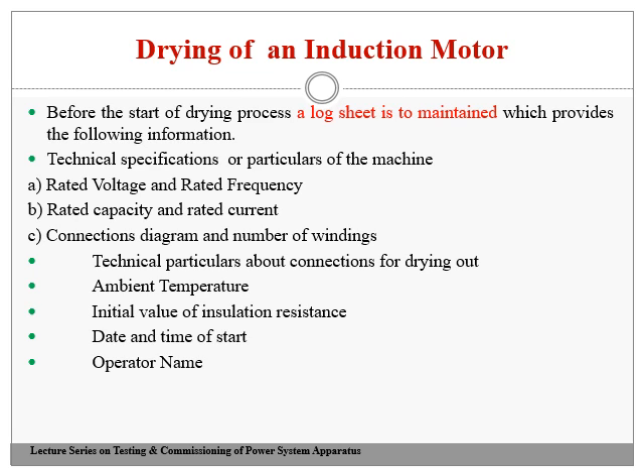Therefore, the technical details of the motor or equipment which comes up for the drying process are noted down in a log sheet. The technical particulars about the connections for drying out, ambient temperature, the initial value of insulation resistance, date and time of start, and the operator name. All this information should be there in the log sheet.